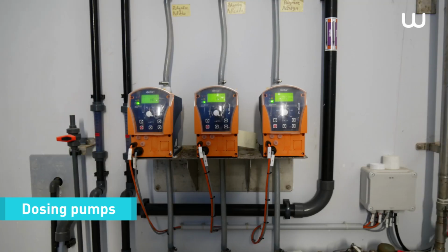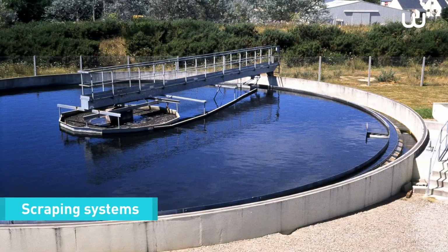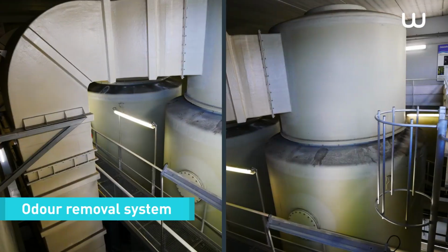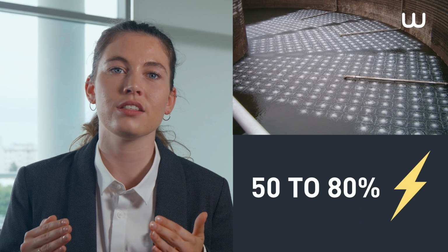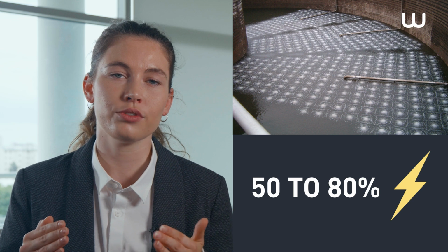What you need to remember: a wastewater treatment plant comprises different electrical and electromechanical equipment such as pumps, agitators or scrapers, sludge dewatering equipment or air treatment equipment that consume electricity. In a conventional activated sludge treatment plant, the system supplying oxygen to biological tanks is the item that consumes the most energy, accounting for 50 to 80% of the activated sludge plant's total electricity consumption.